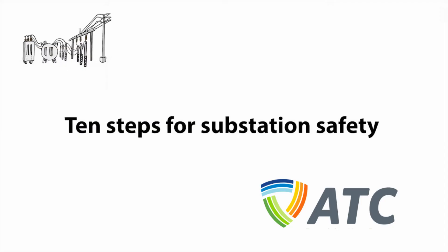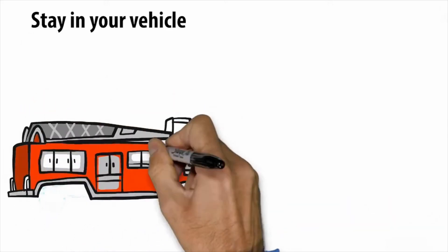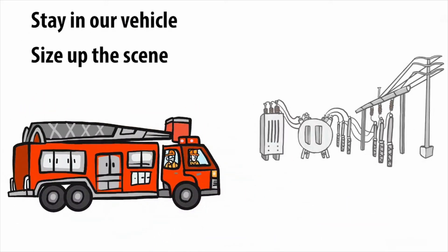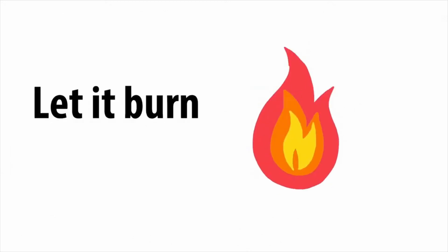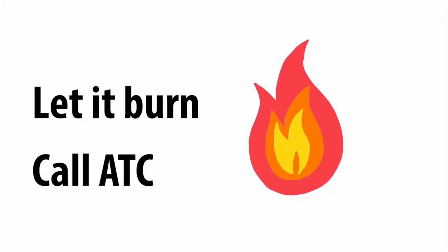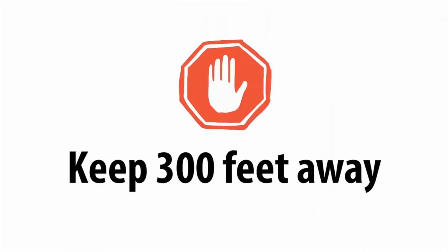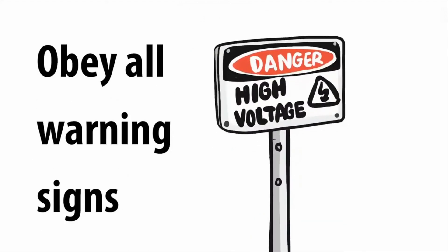Here are ten steps for substation safety. Stay in your vehicle. Size up the scene. Wait for an ATC representative to determine a safe approach. If it's on fire, let it burn. Call ATC. Keep everyone 300 feet away. Obey all warning signs.